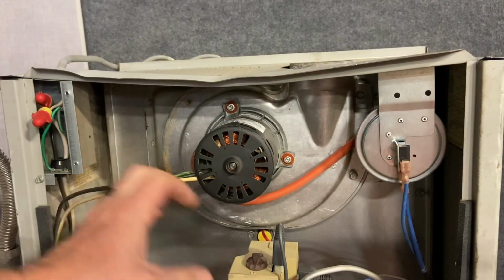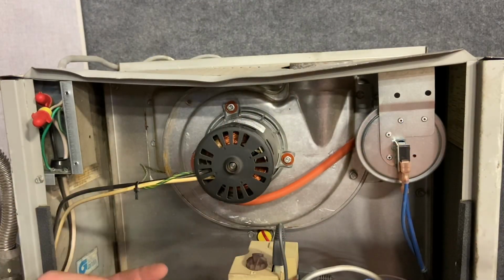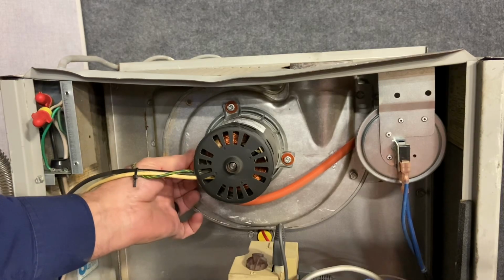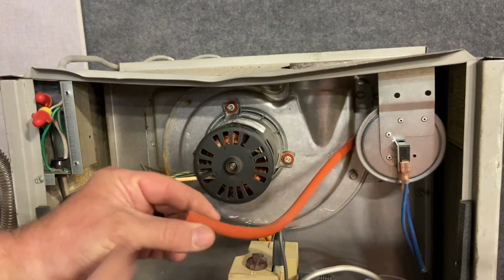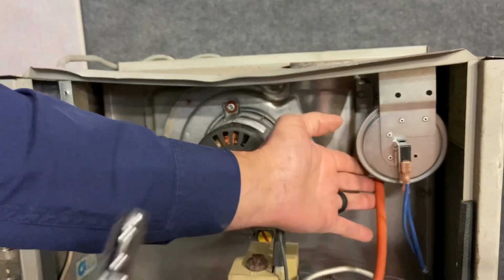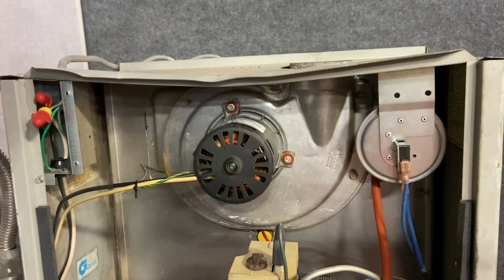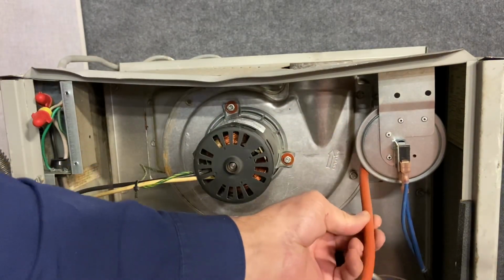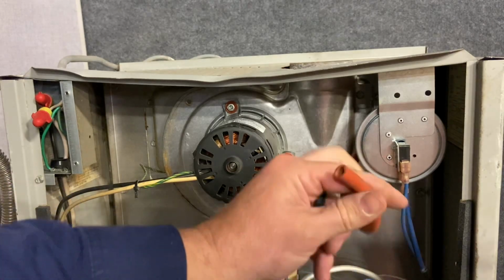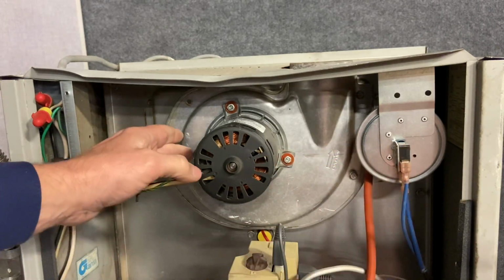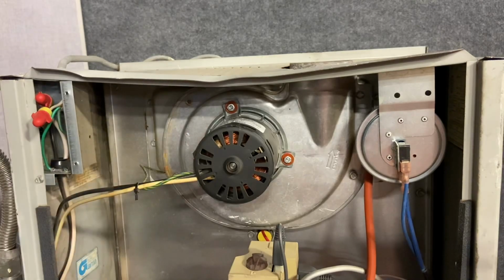So this is our inducer fan assembly. What we're going to do is we're going to pull this off so we can talk about the components, starting with this little hose right here. This is the hose, the vacuum hose to the negative pressure switch or vacuum pressure switch. These hoses get brittle and cracked over time and have to be replaced. This one is fairly cracked and there's a rust, pretty bad rust on the side. Once I pull this off, you can see it.